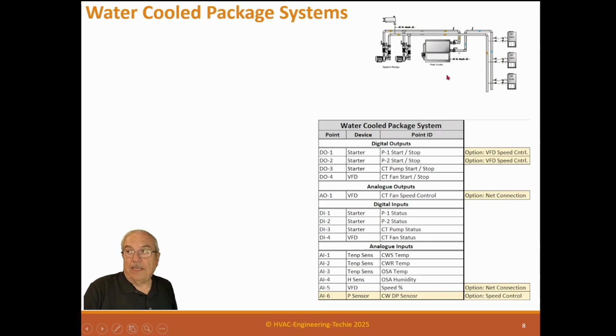And then if you want to make this variable flow on these system pumps, see, I have them constant flow with starters. You can do that. What you do to do that is you have to come out here and you have to put automatic valves on these AC units. So when they're off, that valve is closed. But when it's on, it opens that valve. And that allows flow. So if these two have no flow and this one has flow, and then this one comes on, these two have flow, this has no flow, you can see that's variable flow, right? It runs a variable flow.